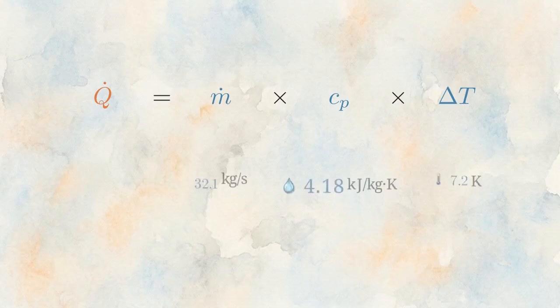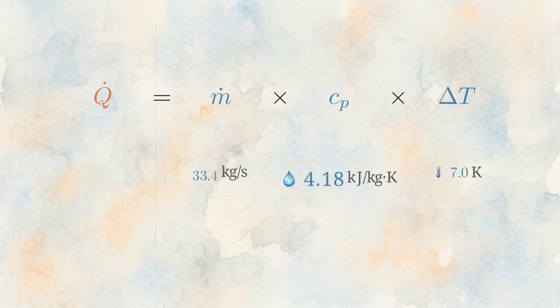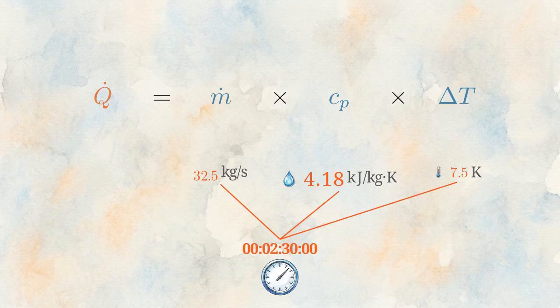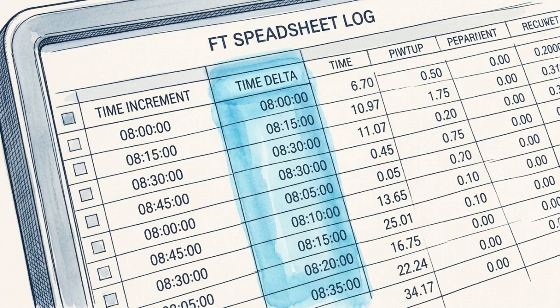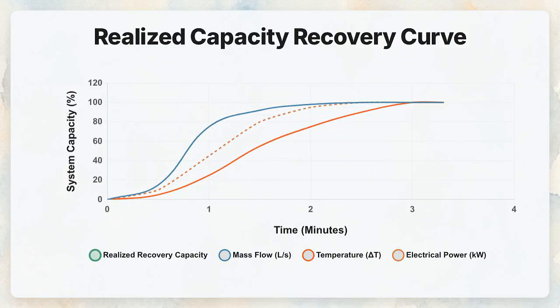To prove actual heat absorption, we rely on a specific thermodynamic equation. The capacity, Q, requires live data inputs for the mass flow of the water, its specific heat, and the precise temperature differential across the evaporator. All three of these variables must be captured and calculated on a single, synchronized clock to be valid. This requires stringent 1-minute measurement and verification tracking. By aligning flow, temperature, and power data simultaneously, engineers can plot the actual, realized recovery curve of the plant's capacity.